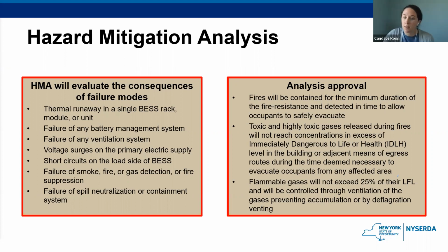So then the fire code official may approve the analysis, provided that the consequences of the analysis demonstrate that fires will be contained for the minimum duration of the fire resistance rating, and detected in time to allow occupants to safely evacuate, that if there's any toxic or highly toxic gases released during fires, they will not reach concentrations in excess of immediately dangerous to life or health level in the building or adjacent means of egress routes, and that flammable gases will not exceed 25% of their lower flammability limit and will be controlled. So this is really taking a high level view of, if there is a failure in the system, what are the responses and what are the consequences?